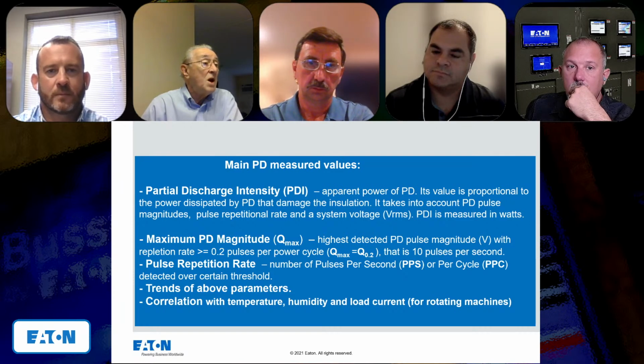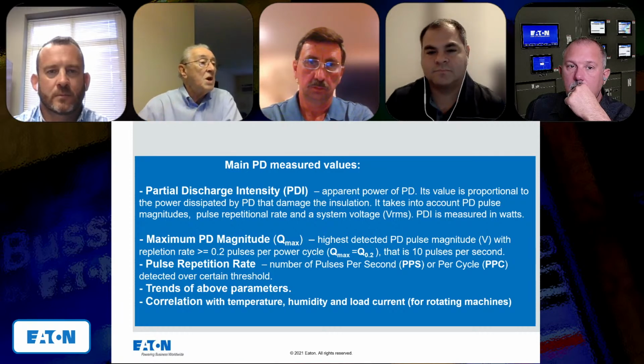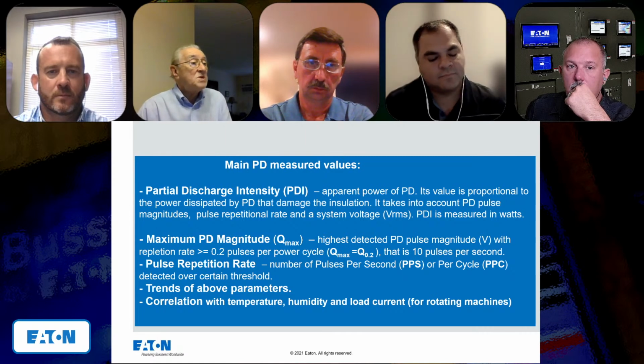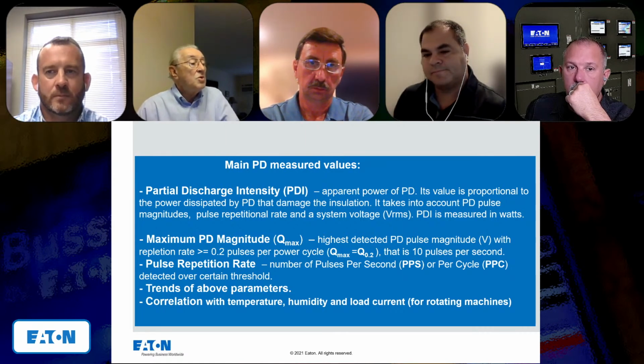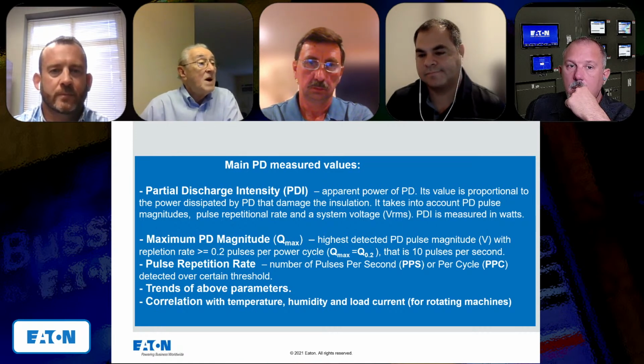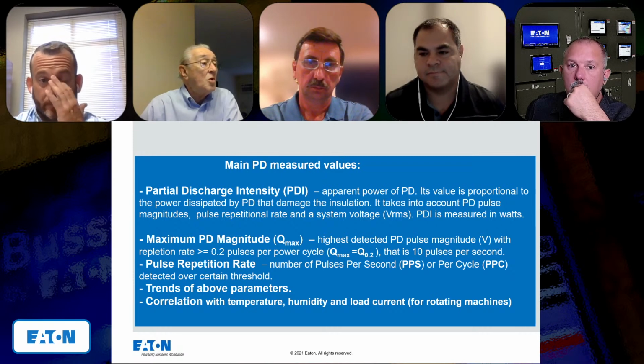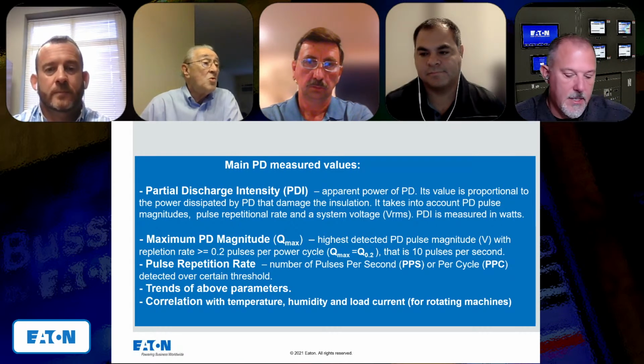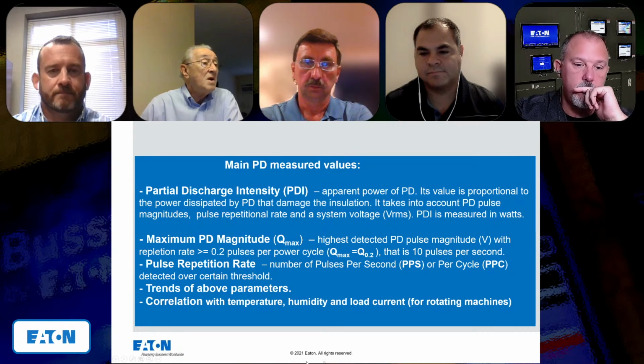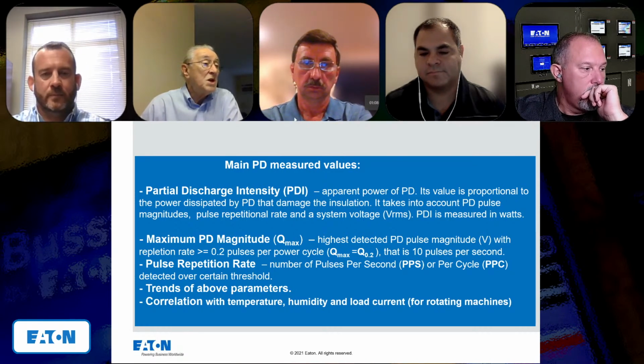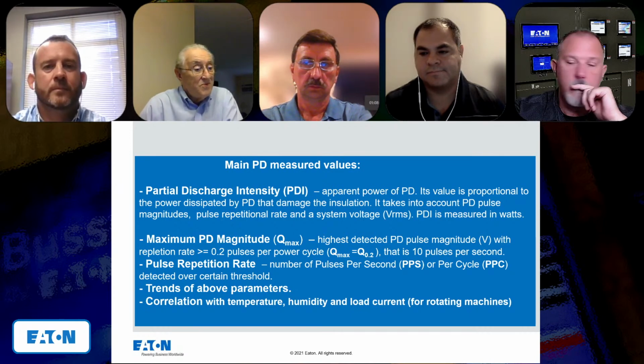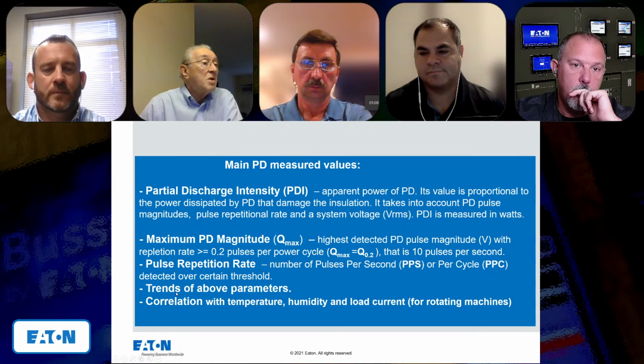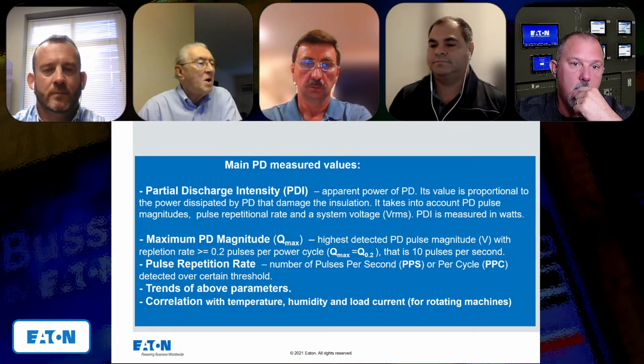Why is it hard? Because partial discharge, when propagated through the equipment, attenuates very fast. So you need to install many partial discharge sensors to monitor complex equipment. Not only one connected, for example, for the bus in the switchgear lines, but it is necessary to install sensors, for example, in each switchgear cubicle.